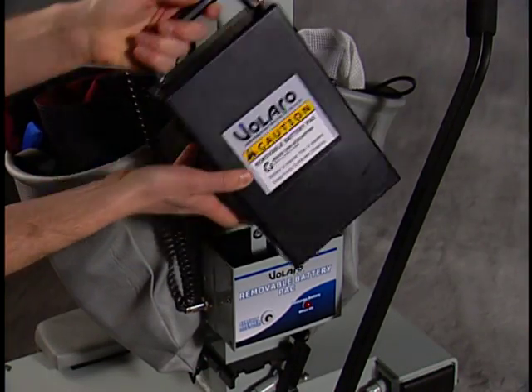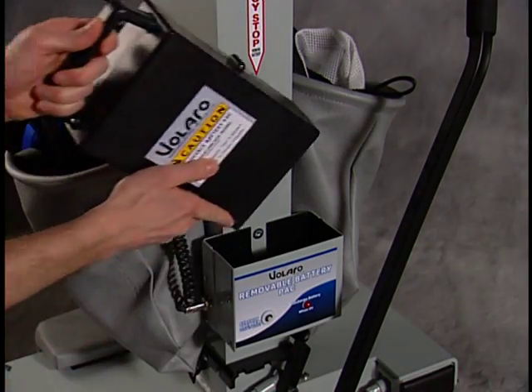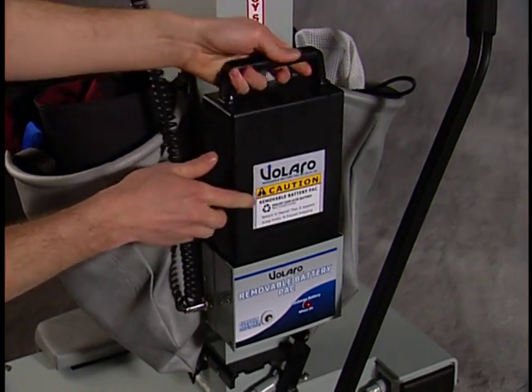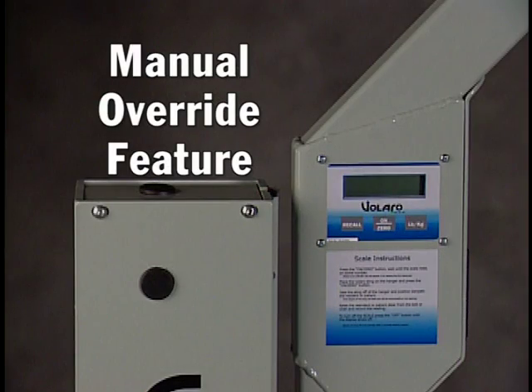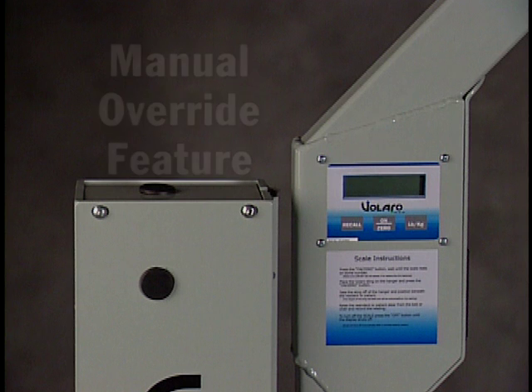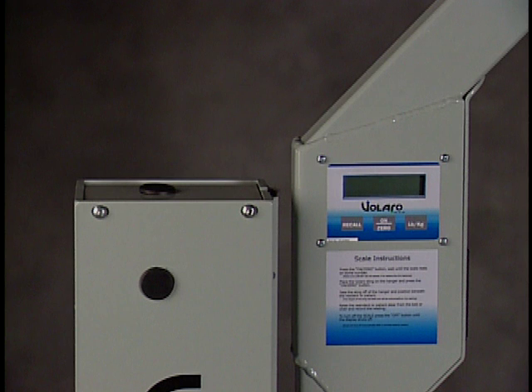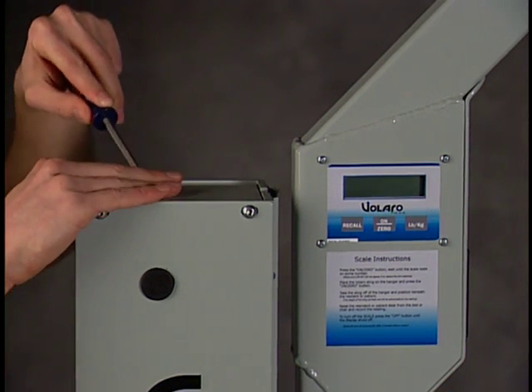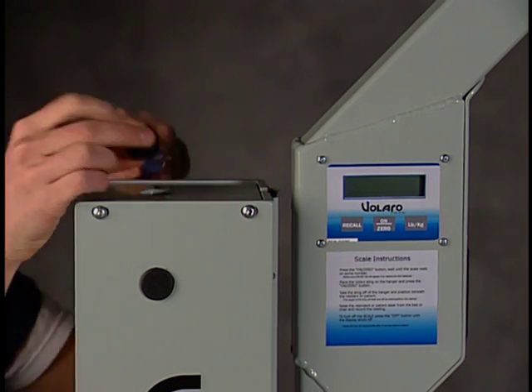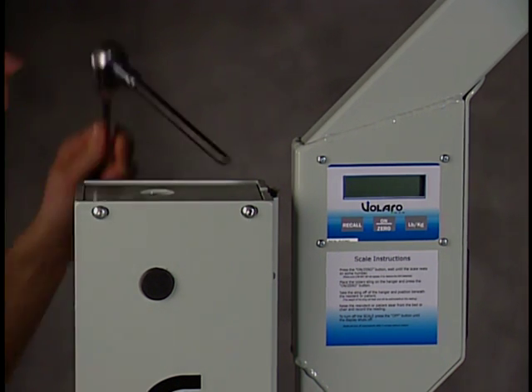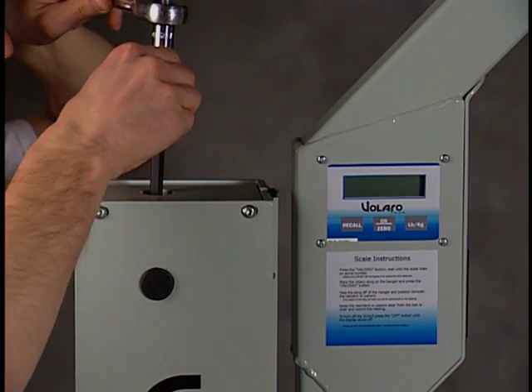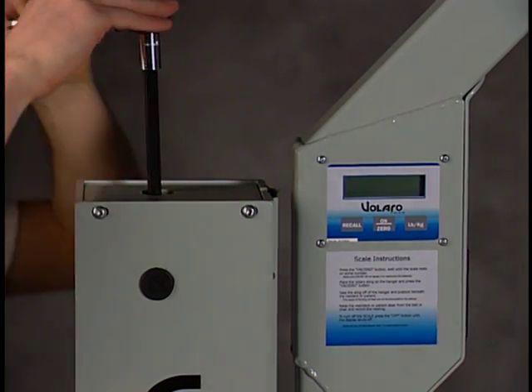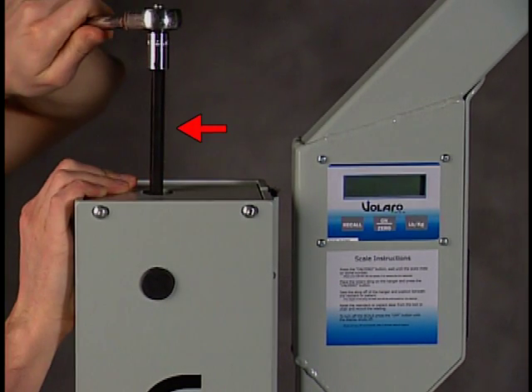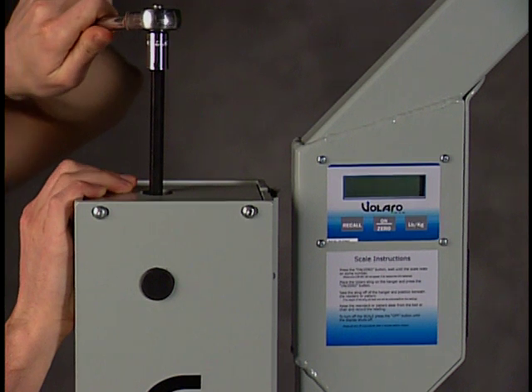If the problem continues, try exchanging the battery for a fully charged one. If the lift still has no power, then it is time to use the manual override feature. To operate the Series 4 full-body lift manually, remove the plastic plug at the top of the lift. Using any 5/16 hex drive, insert the driver into the hex head on the top of the ball screw. For your convenience, SMT provides a 5/16 hex bit with the Series 4 full-body lift.